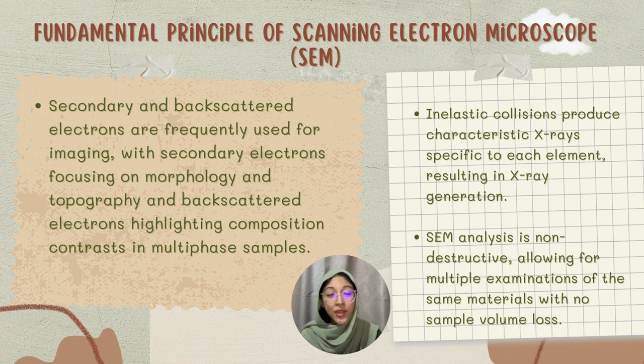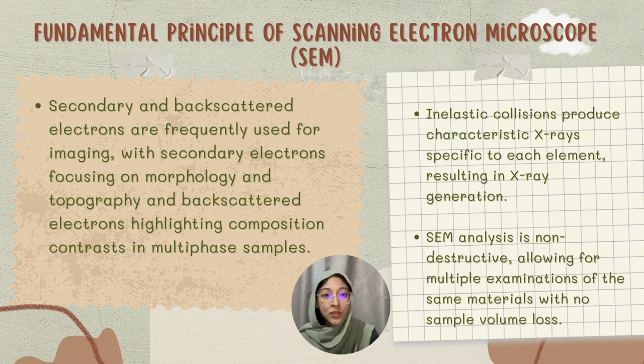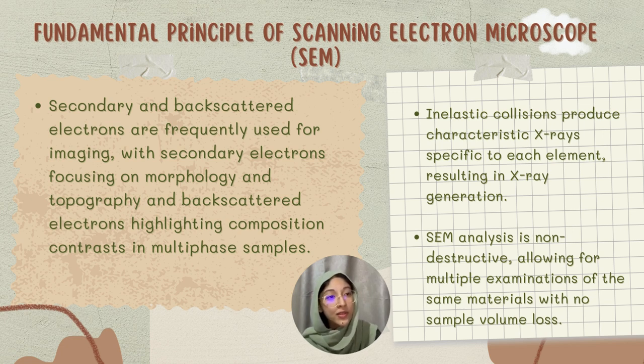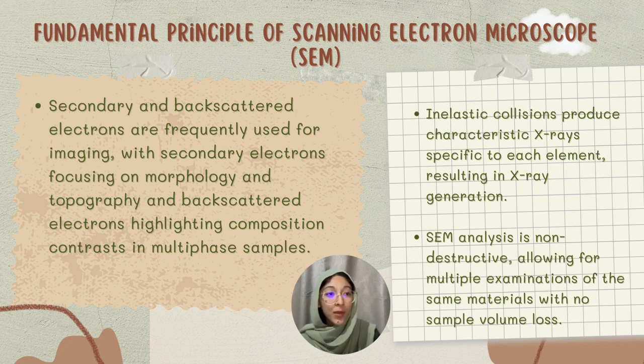Secondary and backscattered electrons are frequently used for imaging, with secondary electrons focusing on morphology and topography, while backscattered electrons highlight composition contrast in multi-phase samples. Inelastic collisions produce characteristic X-rays specific to each element, resulting in X-ray generation. SEM analysis is non-destructive, allowing for multiple examinations of the same material with no sample volume loss.